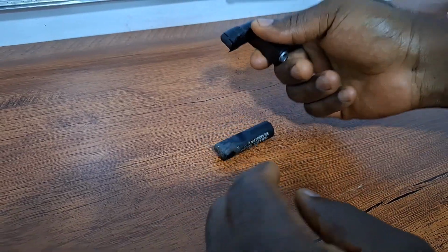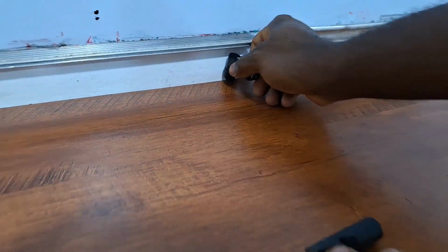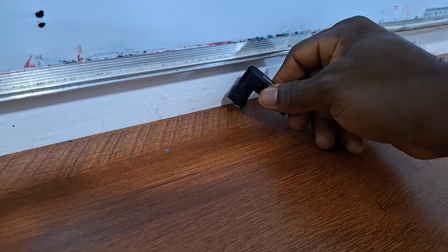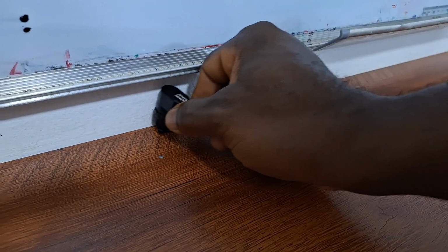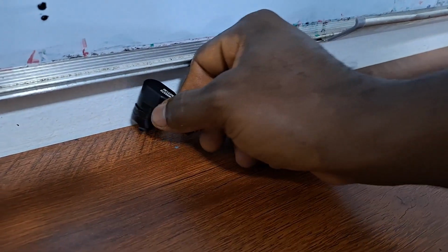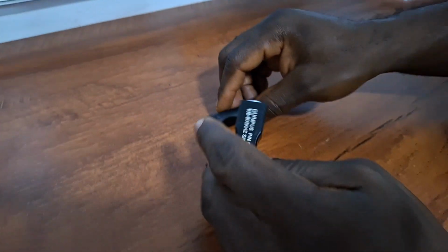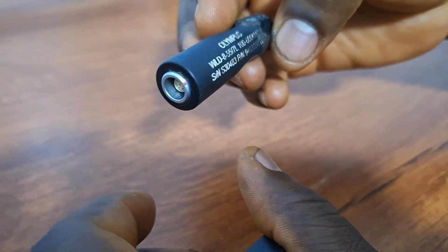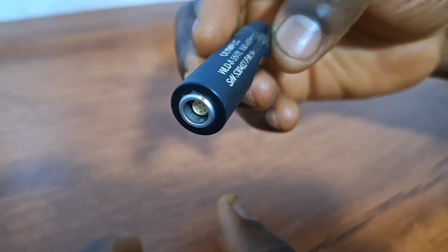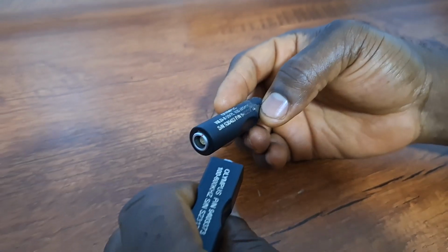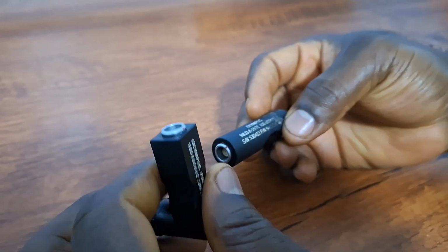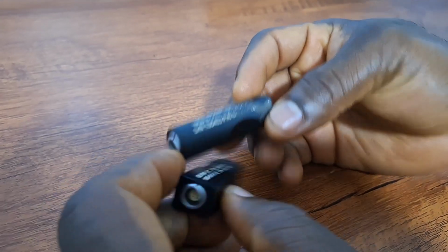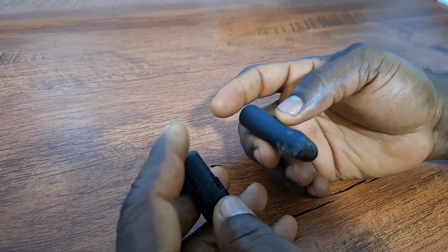Looking at this wall now, it's easier for me to use this configuration if this wall is my weld, to scan a weld that is around this area. The frequency for this is also about 100 to 600 kilohertz, similar to these ones. So that's the bridge weld probe.